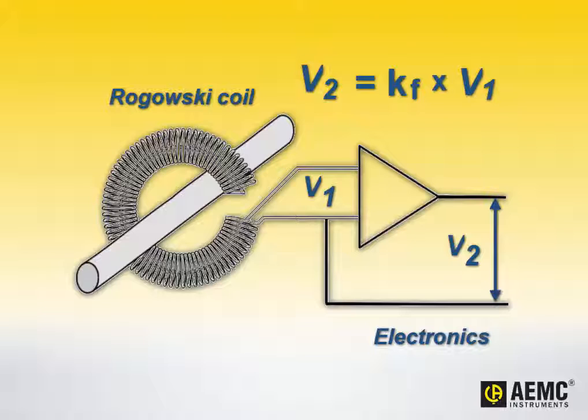In this formula, Kf is a value derived from the physical characteristics of the coil for a given frequency. V2 can then be used to calculate the associated current by applying a frequency-independent scale factor, such as 1 millivolt equals 1 amp.